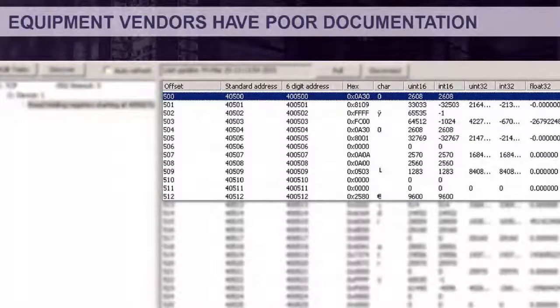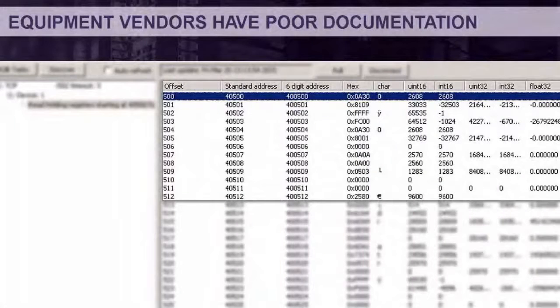So we had to play detective. This is the process we'd go through: we'd crawl a device with Modbus and get data back, then we had to guess what the different registers meant. This is an air handler, and I challenge anybody to look at this screen and figure out what those registers mean. We'd come up with a theory, say we think this register means this, then go to the device and try to prove out that theory, iterating until we'd mapped the entire device.